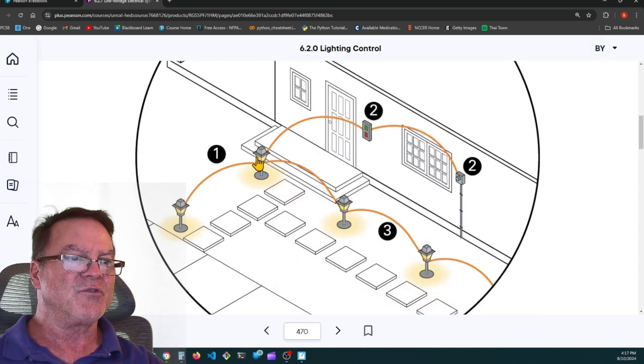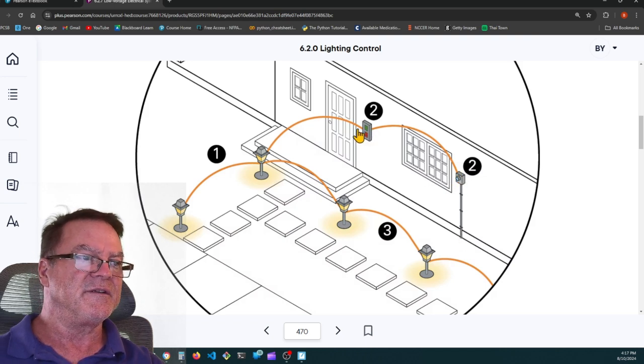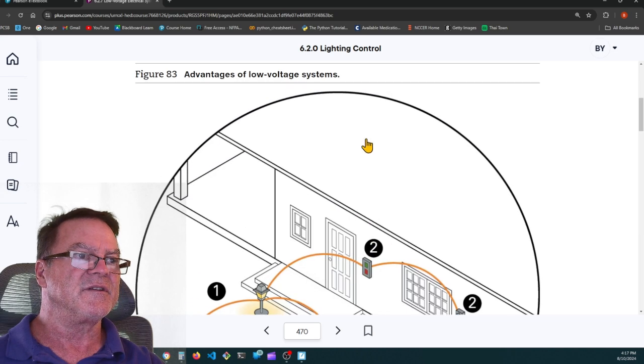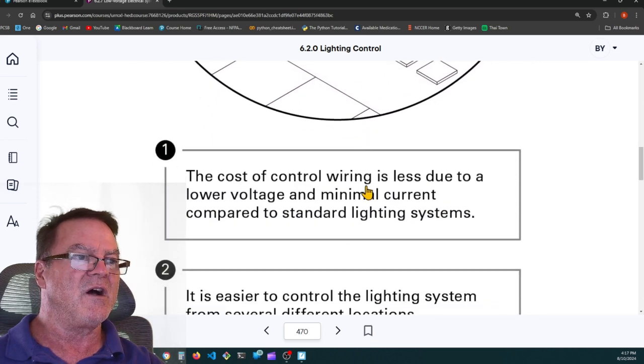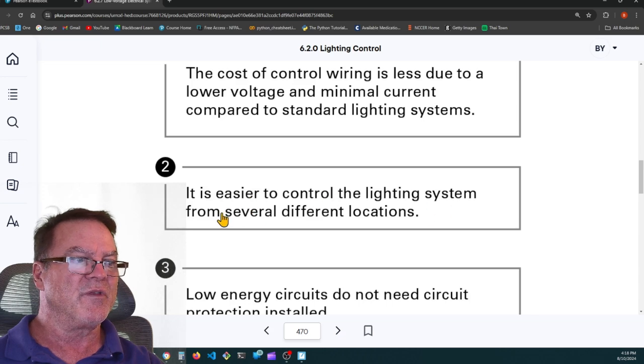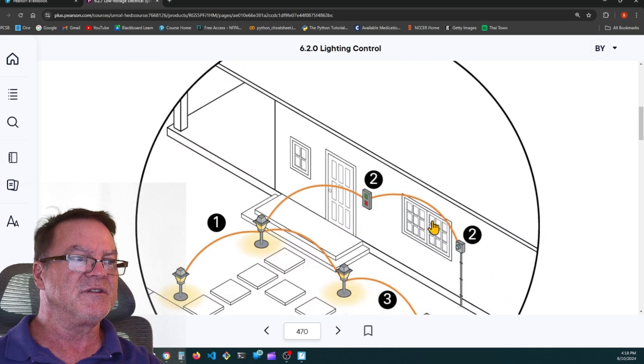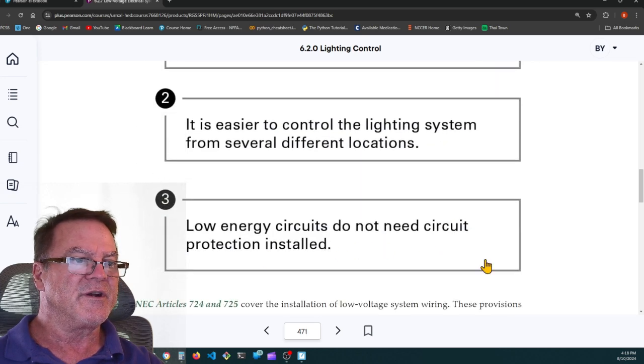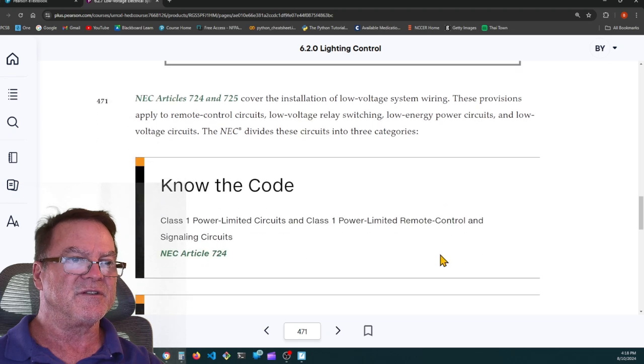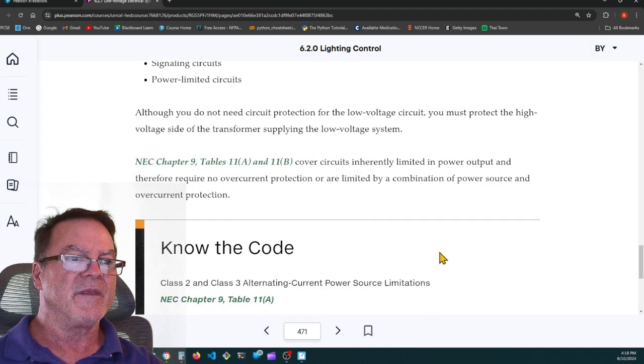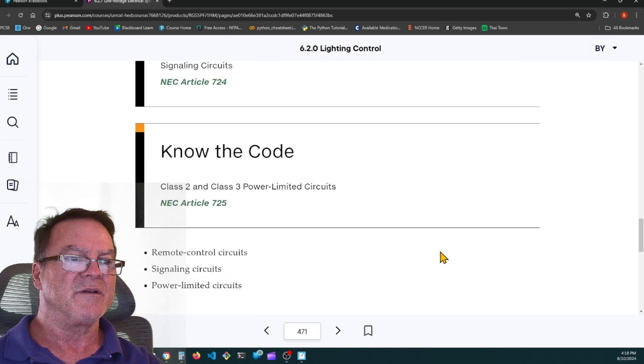So here's outdoor lighting, and it's low voltage. Here's a photo eye, and here is, I think, a timer. Let's see what they say here. What do they have here? One, the cost of control wiring is less due to the lower voltage and minimal current compared to standard lighting systems. Two, it's easier to control the lighting system from several different locations. So here are two different locations. And three, low energy circuits do not need circuit protection installed. All right, let's see what else.